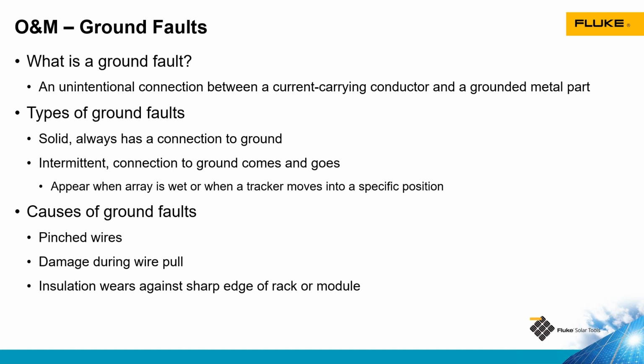Pinched wires, say between a module frame and a piece of racking, are very common causes of ground faults. We can also damage the wires when we're pulling them through the conduit. If we have wire that's not properly managed and the insulation is rubbing up against a piece of racking or maybe the corner of the module frame, over time, that insulation is going to wear away and is going to cause a ground fault.